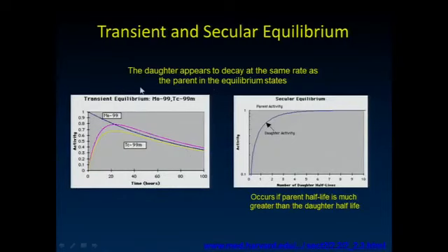And if you have the generator, one of the things that's really nice about it is if you start off with no technetium and just your molybdenum, and you watch after about a 24-hour period, you reach a peak in the amount of technetium that's available there. So you can take all the technetium from the generator and then let the next 24-hour period go on where, again, that amount of technetium was going to rise over time as that molybdenum decays until it's time to elute the generator once again.